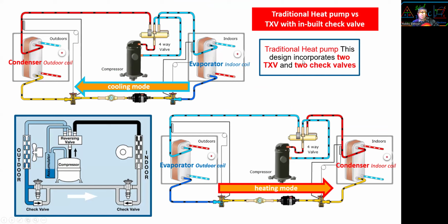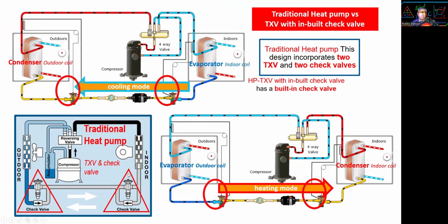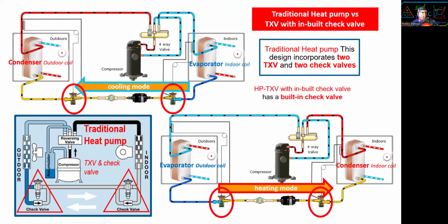Traditional heat pump: you have 2 check valves and 2 TXVs for bi-flow, for reverse. But with the built-in check valve, you eliminate the check valves.